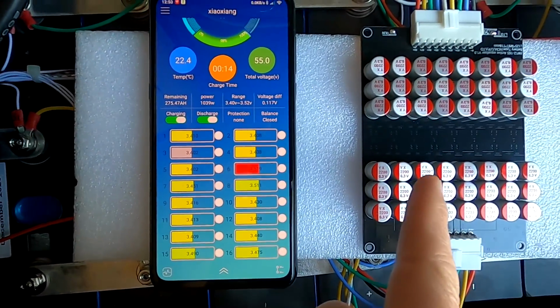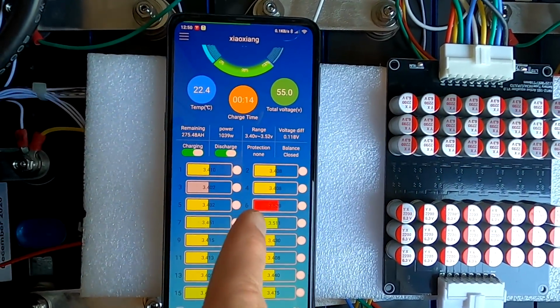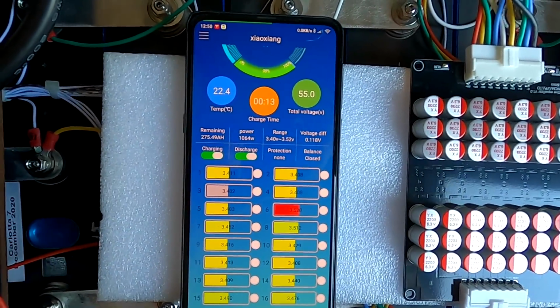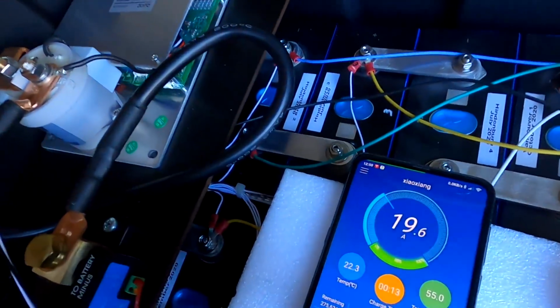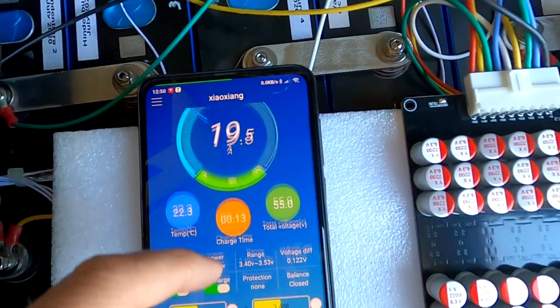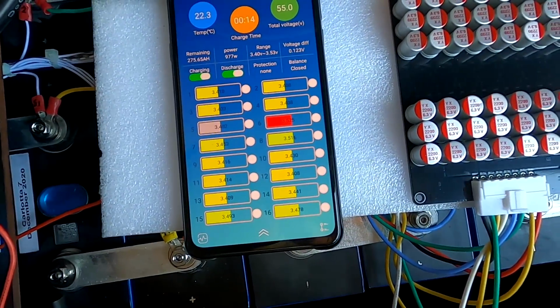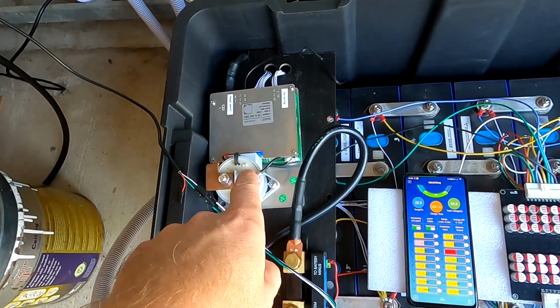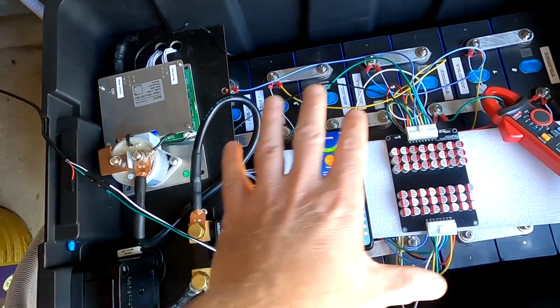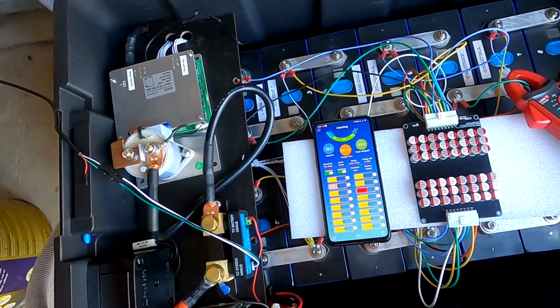Still, the balancer seems to prevent the battery from getting single cells too high, and the BMS from turning off. Because this was exactly happening before, when we had only the BMS connected to the battery, with its low 150, 200 milliamps of balancing current max, and it was not able to keep the cells under control at this point of charge. We're still charging with 20 amps here into the battery, so fairly high charge current, and the BMS, the QUCC BMS, was not able to control the battery anymore in such a situation.